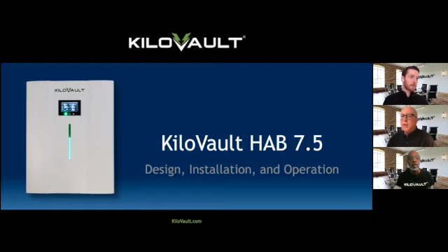There's a great question here from Gail. In commissioning, can the phone, phone in quotes, be one that can only interface with a Wi-Fi signal but not have cell service? So if you're out in a remote location, can you still communicate with the HAB with a phone? And I think the answer is through the way we were just talking about, right? Yes, you would be connecting to the HAB doing local connect. You'll connect your mobile device to the HAB's Wi-Fi. It creates its own local access point. That way you can view the HAB's information on that local device without having to connect out to the cloud.